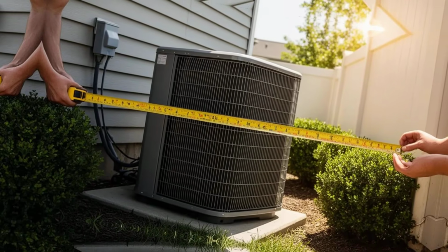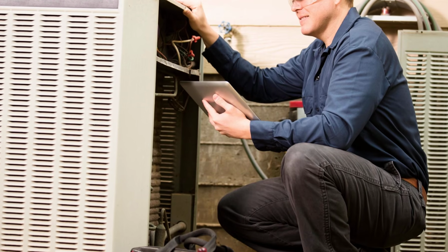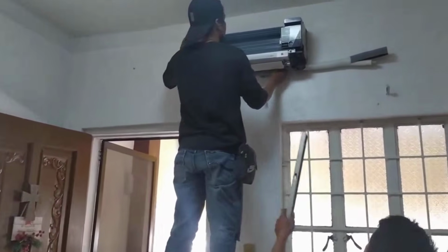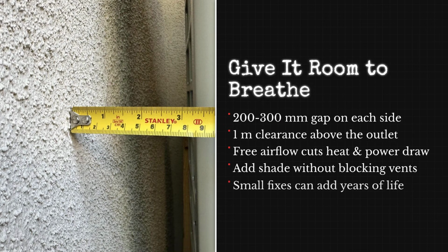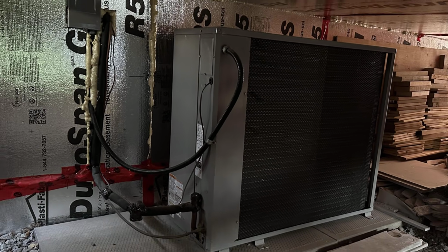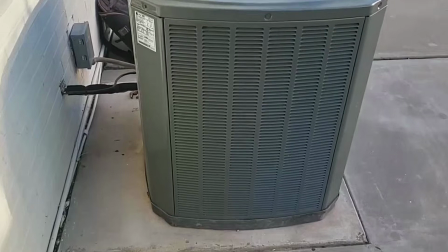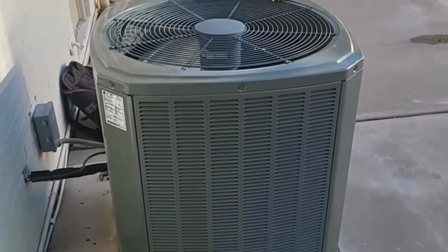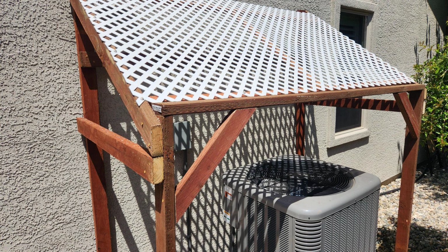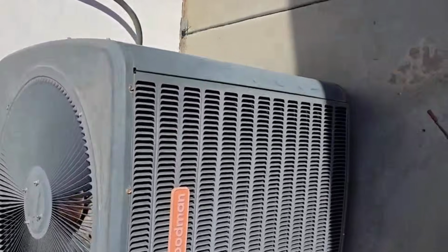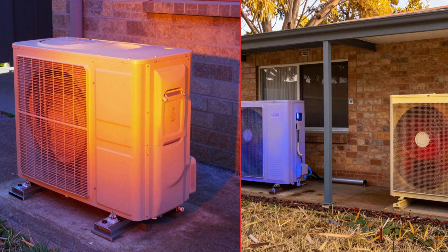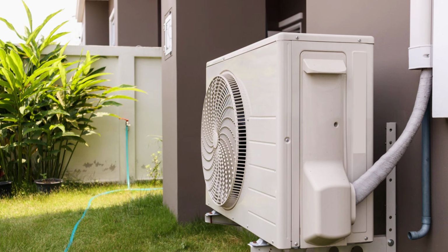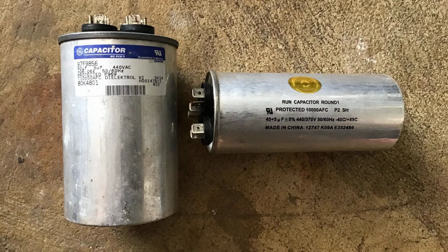Check your outdoor unit clearances against the manufacturer's specification. It is in the installation manual. I know you have not looked at it because nobody looks at the installation manual. The minimum clearances are typically 200 to 300 millimeters on the sides and 1 meter above the outlet. If yours is sitting in a slot that makes those clearances impossible, talk to your technician about relocation options. Add some shade over the outdoor unit where you can, without restricting outlet airflow. A shaded condenser in a Western Australian summer can run 5 to 8 degrees cooler than an unshaded one. 5 to 8 degrees over 10 years of operation is a meaningful difference in component life.